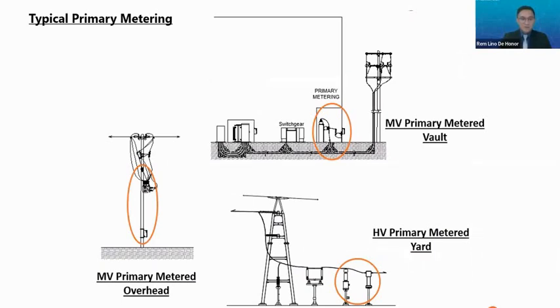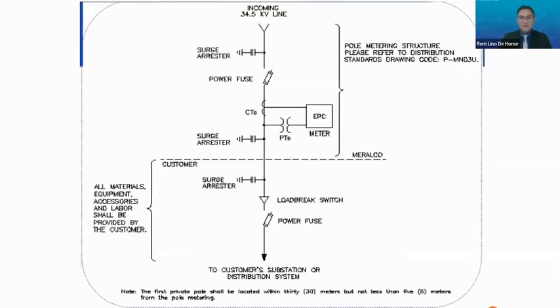For the first photo, medium voltage primary meter overhead. The second photo is the medium voltage primary metered vault. And the last photo is the high voltage primary meter yard. The diagram shows the standard primary metering. Please take note that the first private pole shall be located within 30 meters but not less than 5 meters from the metering pole.